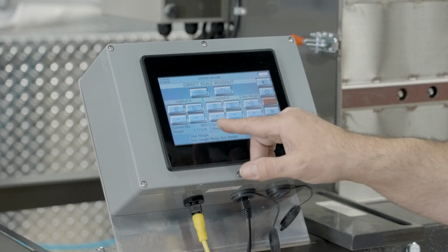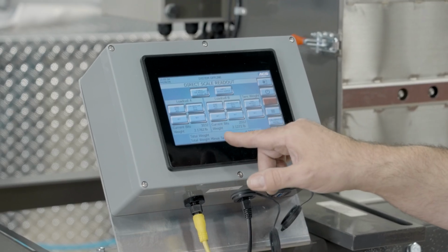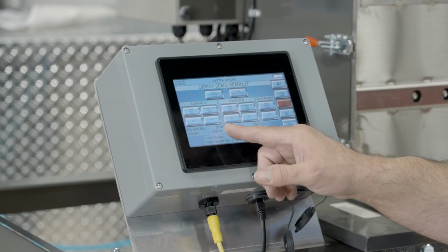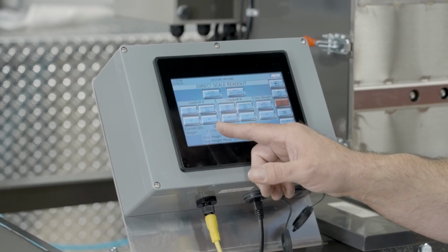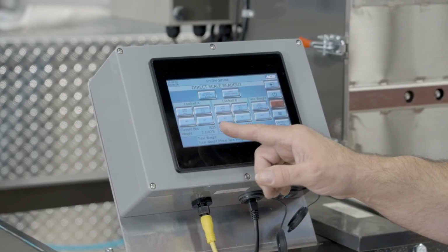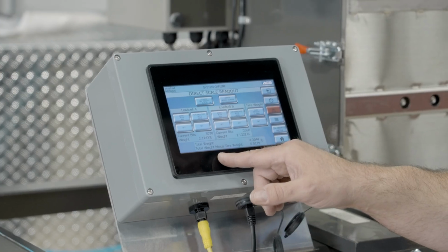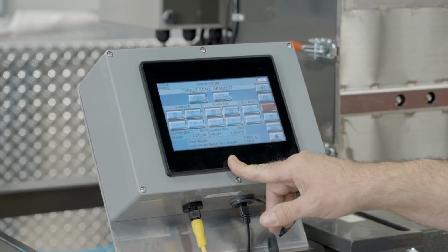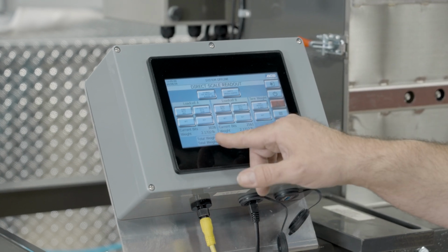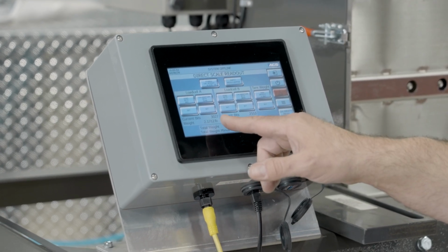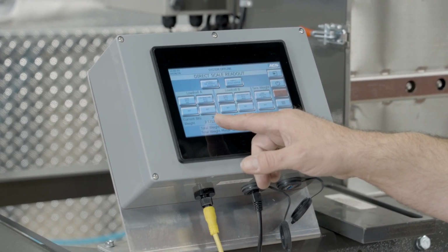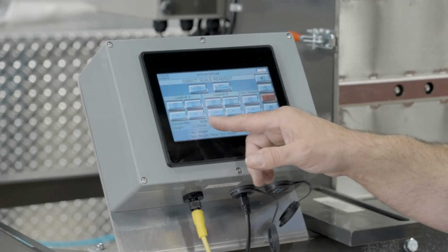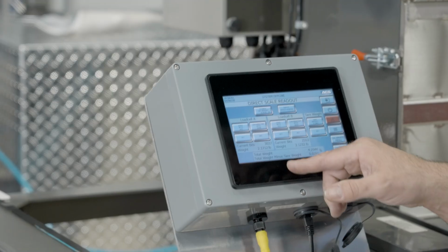These numbers correlate to the signal coming from your load cell. If you look right now, we have 3028 bits. Basically that means you should see 3 millivolts DC coming from your load cell, and it converts it to a digital signal inside the PLC. But this is a good troubleshooting aid. A lot of times when your load cells go bad, you'll see this value either read 0 or read very high, like 20,000, with no weight on it, and that's a good indication that you have a bad load cell.